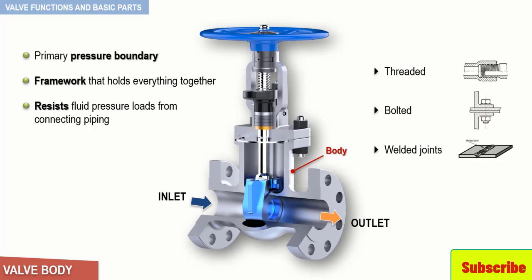Valve bodies are cast or forged into a variety of shapes. Although a sphere or a cylinder would theoretically be the most economical shape to resist fluid pressure when a valve is open, there are many other considerations. For example, many valves require a partition across the valve body to support the seat opening, which is the throttling orifice.